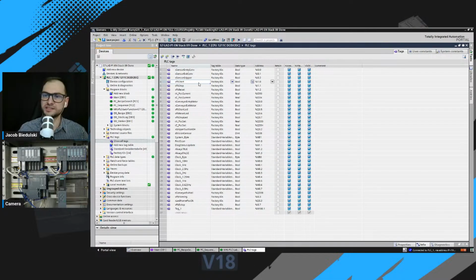So in our courses, for learning purposes, we use Hungarian notation, which means that we use special prefixes depending on the data type of the variable. For example, for Boolean variables, we use X. For integer, we use I. For real, we use R. And for byte, we use B, and so on. And the second standard that we use is camel case. And this is a really good standard in combination with Hungarian notation with those prefixes.